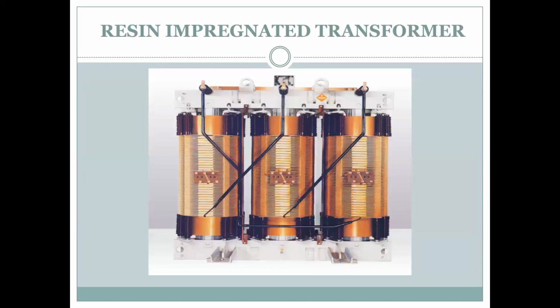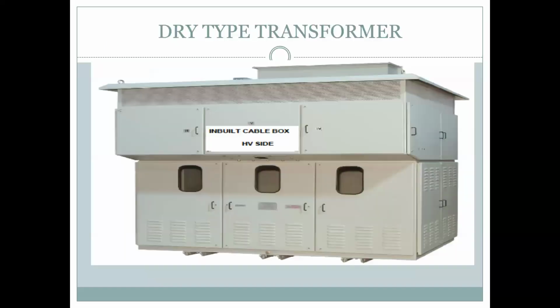Next, we use the vacuum resin impregnated type. Here there is nothing flammable available except resin. The flash point of the resin is much higher compared to oil, so there is no problem with that. Next, so it looks like that. It just looks like a panel. There are no oil related activities in that. So it is very clean and environment friendly, and it is called a green transformer, and it does not give any activity related to oil. Next.